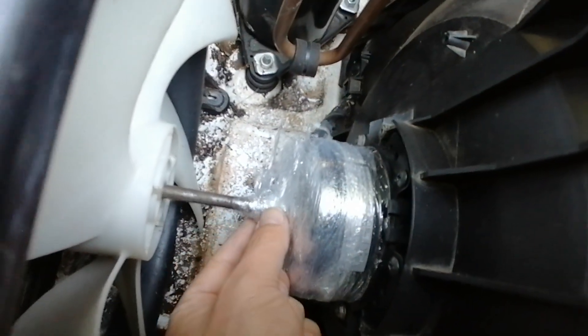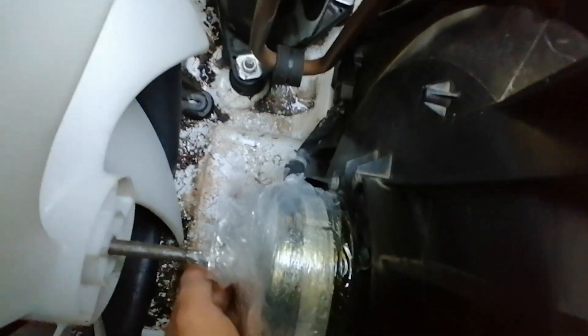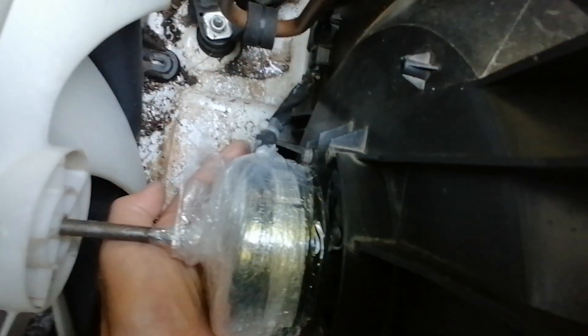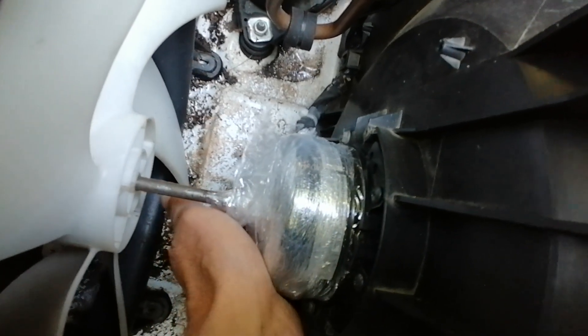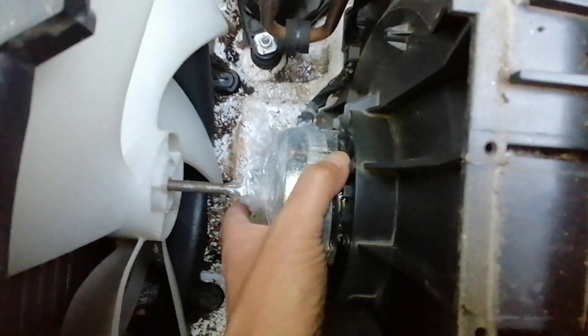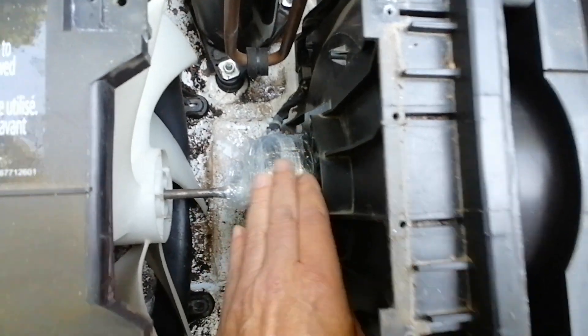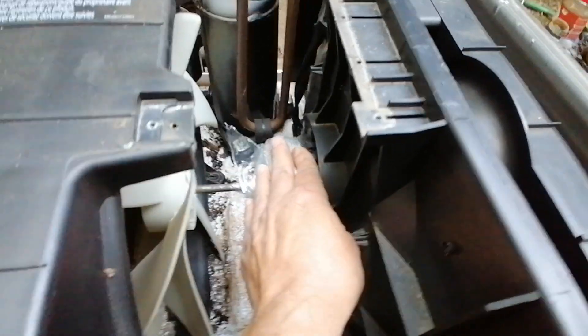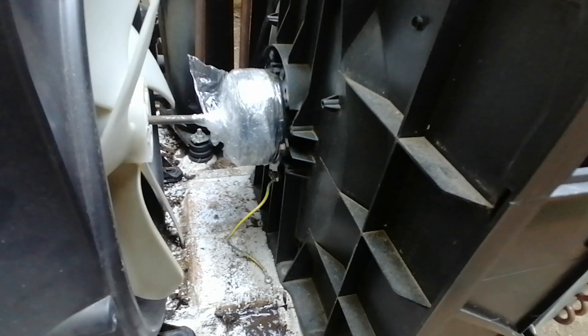You want to wrap where the shaft is going in and wrap around the wires. There's also a weep hole underneath the motor — not always, but most of them have one. I don't feel one on this side but it might be on the other side. Water does get into these motors quite easily.